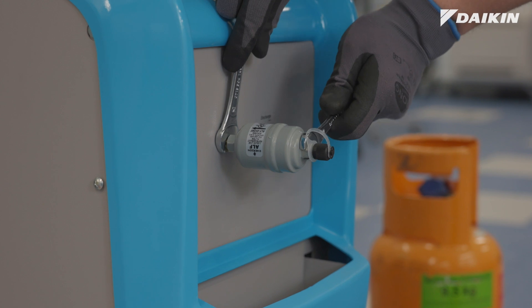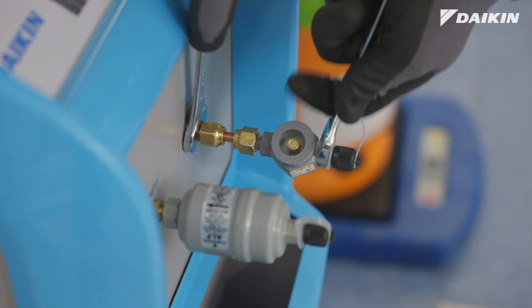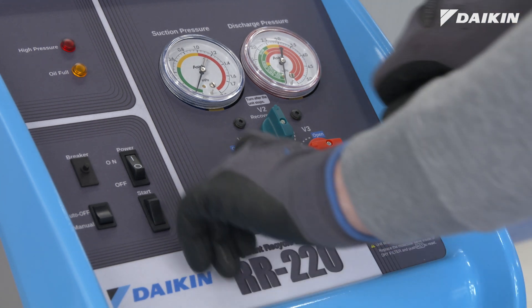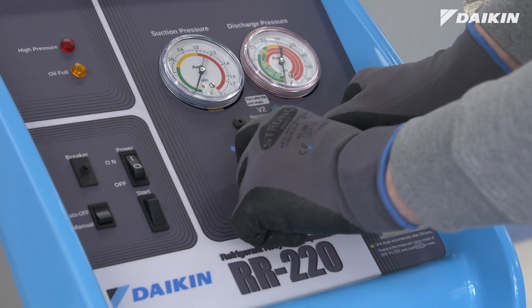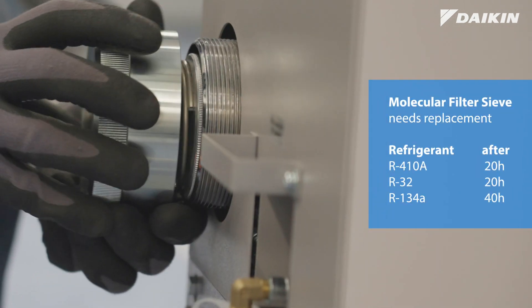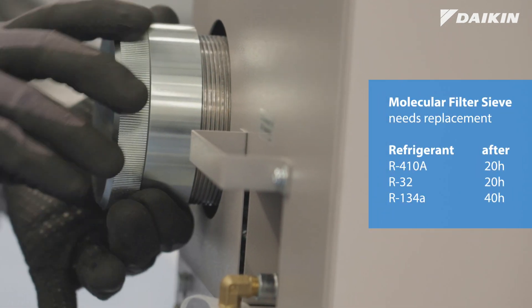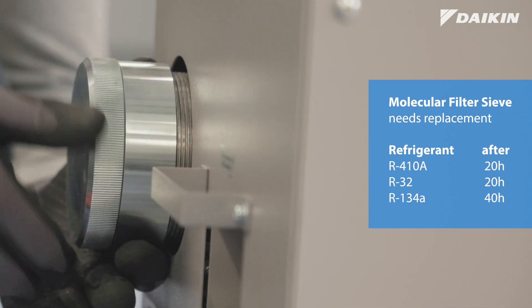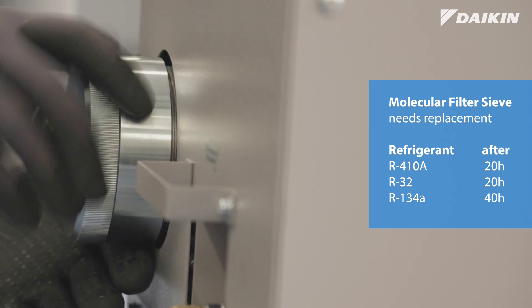Then, connect the filter dryer and sight glass to the unit. When using the unit for the first time, release the nitrogen from the unit and insert the molecular sieve. The sieve has to be replaced every 20 hours of operation when recovering R410A and R32, and every 40 hours when recovering R134A.